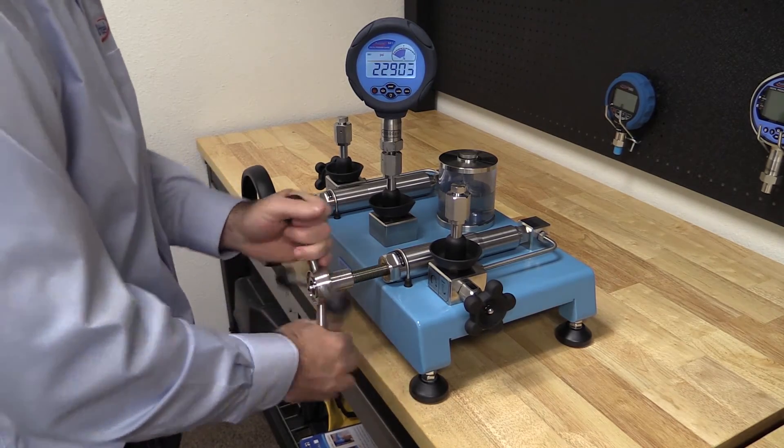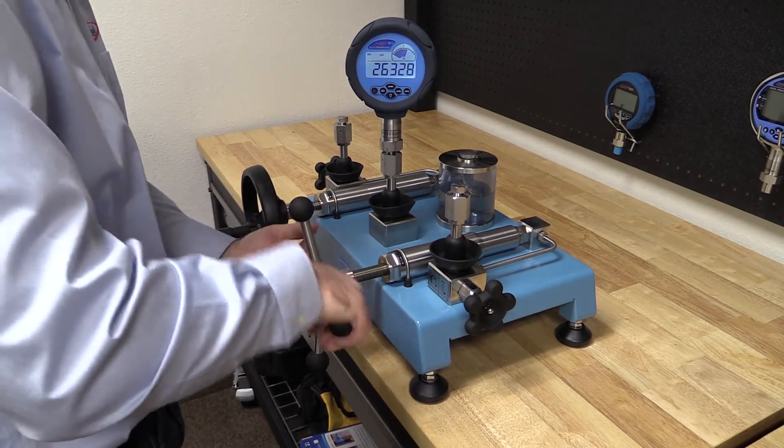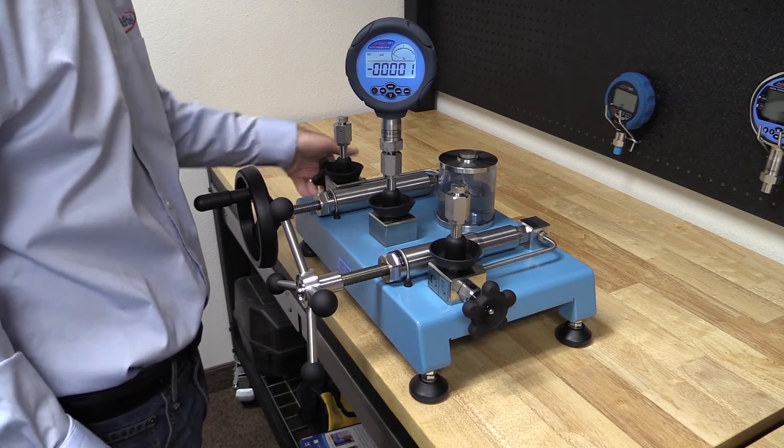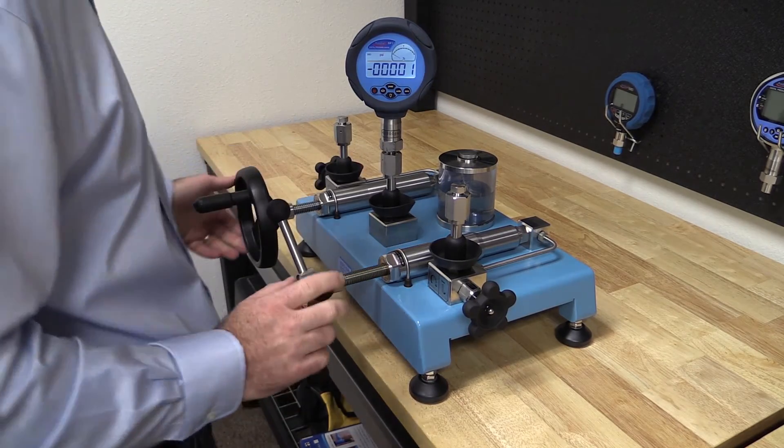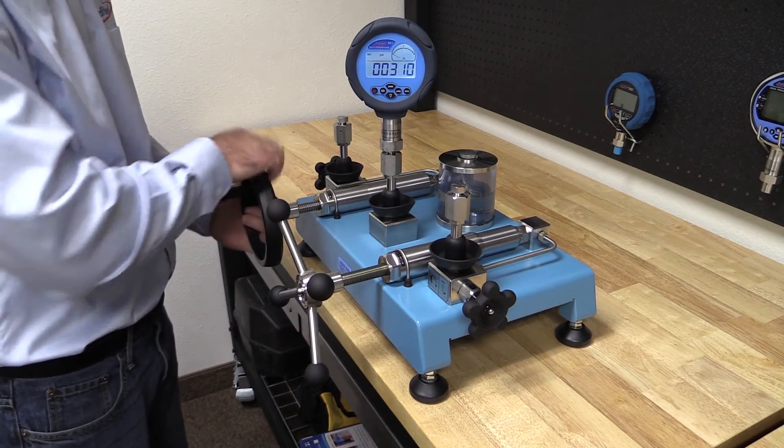You should easily be able to generate full scale pressure with less than half the stroke of the screw presses. If I want to generate 40,000 psi, for example, I would close the vent valve and screw in the pre-pressure screw press until about 5,000 or 6,000 psi.